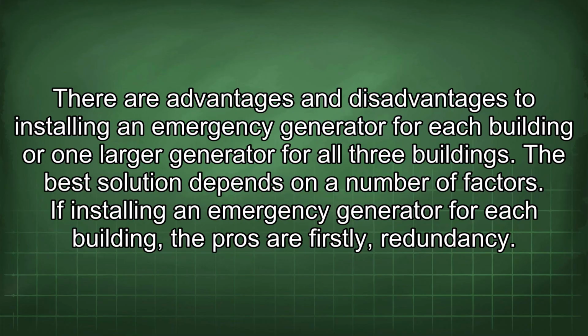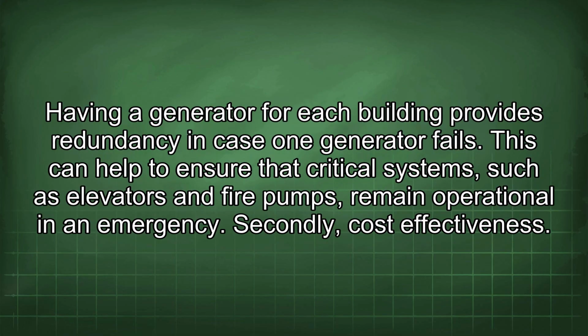There are advantages and disadvantages to installing an emergency generator for each building or one larger generator for all 3 buildings. The best solution depends on a number of factors. If installing an emergency generator for each building, the pros are, firstly, redundancy. Having a generator for each building provides redundancy in case one generator fails. This can help to ensure that critical systems, such as elevators and fire pumps, remain operational in an emergency.